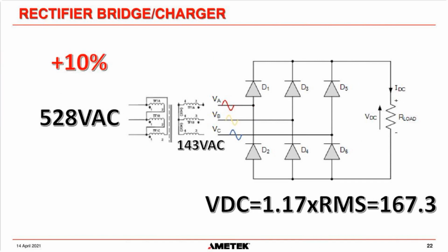And similarly, if we go up 10% to 528 volts, our secondary will go up proportionally to 143 volts, and our DC on the output will now go up to 167 volts, which could overcharge your batteries. And if they were valve regulated batteries, they could go into thermal runaway.